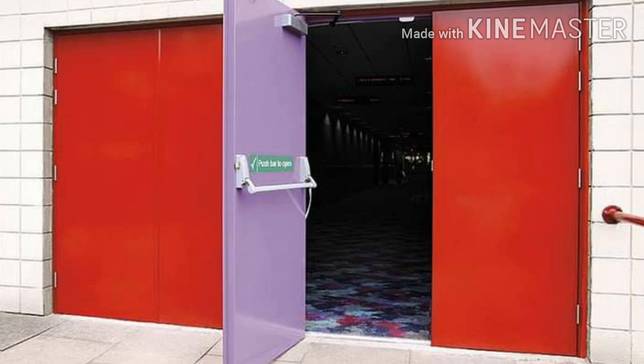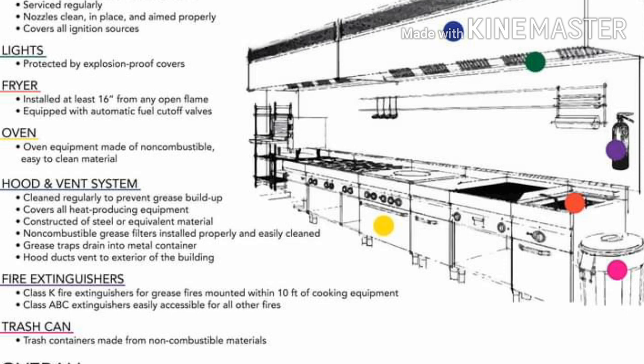Kitchen, laundry, linen stores and furniture storage shall be of fire resisting construction, and you have to follow that, provided with 1 hour fire resisting self-closing doors. Transformer bays, HT and LT supply rooms, air conditioning plant systems and boiler rooms shall be separate fire resisting rooms and shall conform to National Building Code of India 1983 fire protection rules. Special hazards due to LPG shall be in accordance with the provisions of National Building Code of India 1983 also. And the air conditioning system shall conform to Indian Standard 1642-1989, and it shall be further linked with the fire detection system to automatically cut off the respective floor AHU in case of fire.